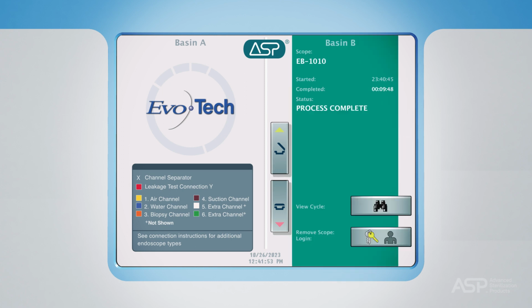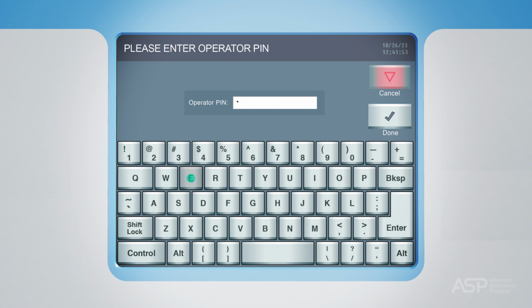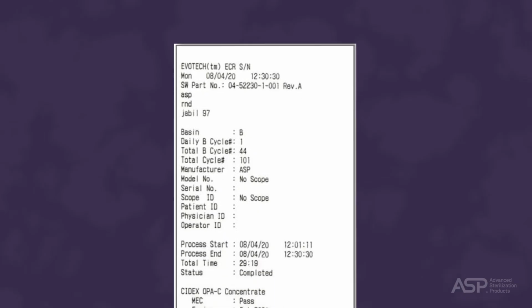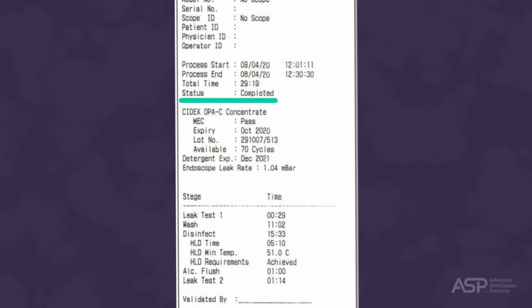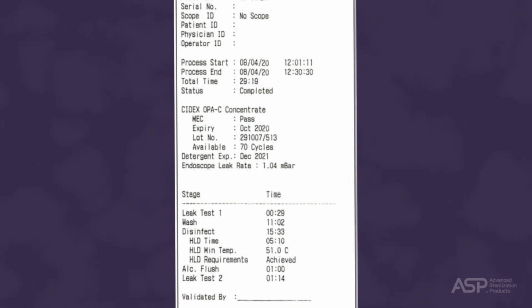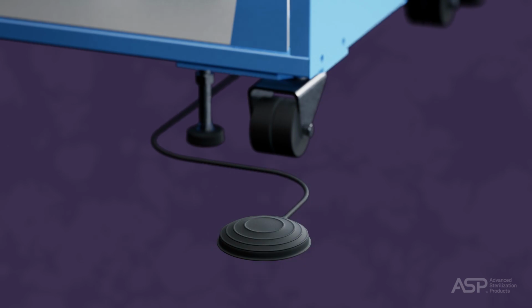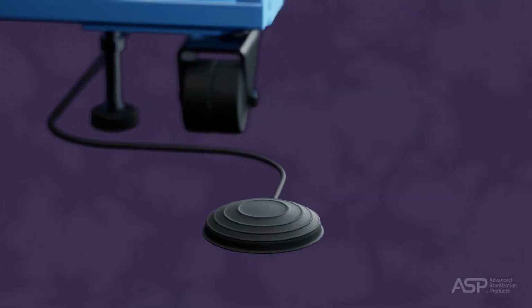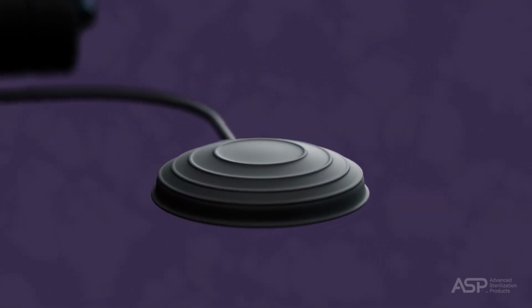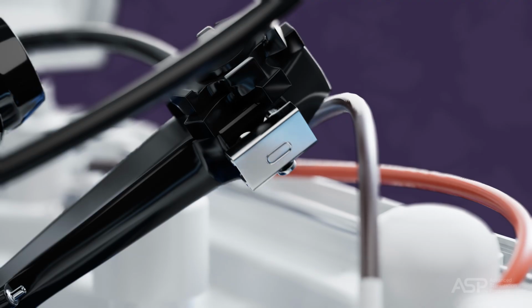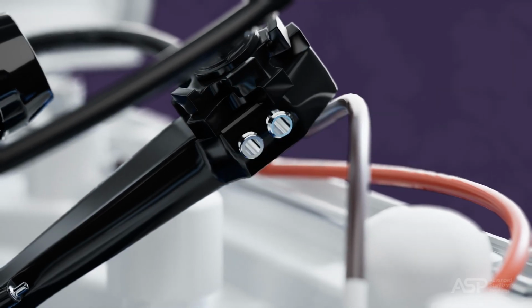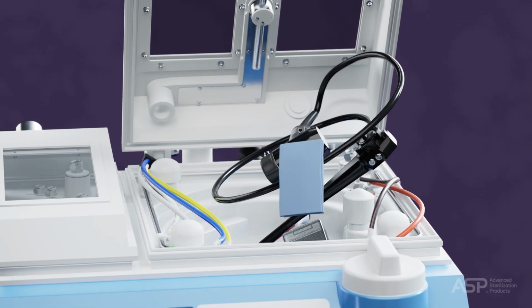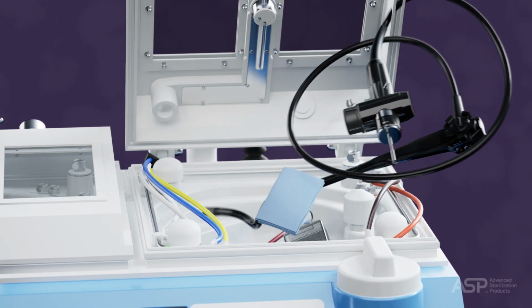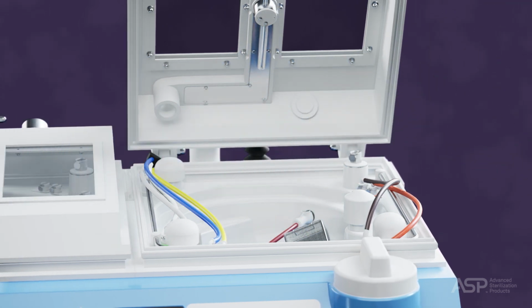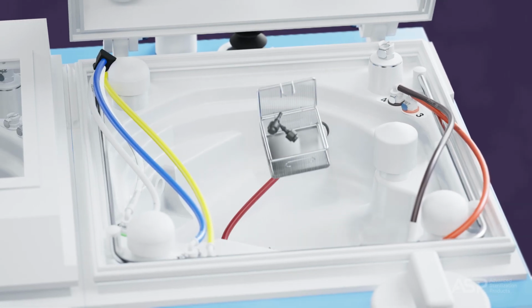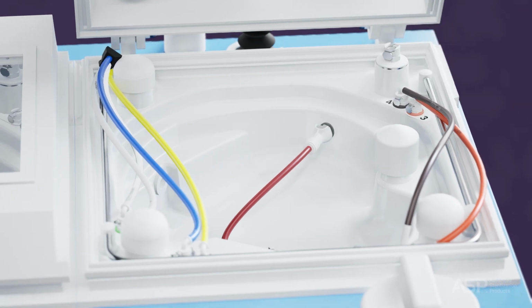To complete a cycle with clean hands or gloves, enter your user identification PIN. Review the cycle printout and verify that the process was completed, the MEC was met, and HLD was achieved. Open the lid with the foot pedal or by pressing the Lid Open button on the screen. Disconnect the endoscope connectors, including the channel separator if applicable. Then gently remove the endoscope while drying it with a lint-free towel. Dry and store the endoscope following facility procedures. Finally, remove any accessories from the mesh basket and store them according to your facility's policy.